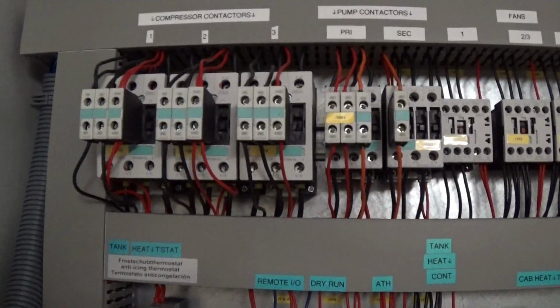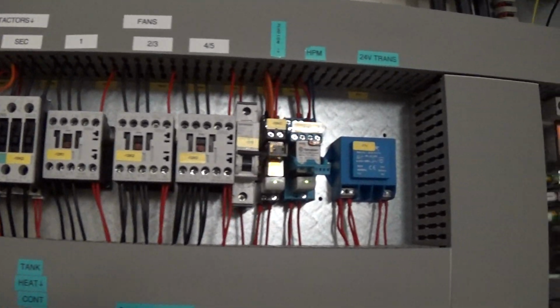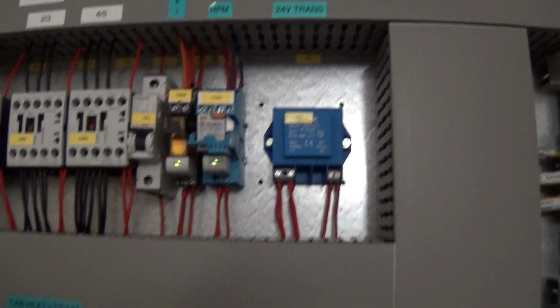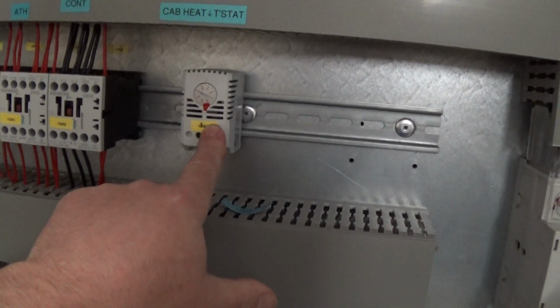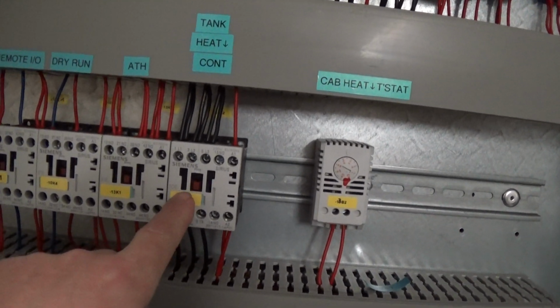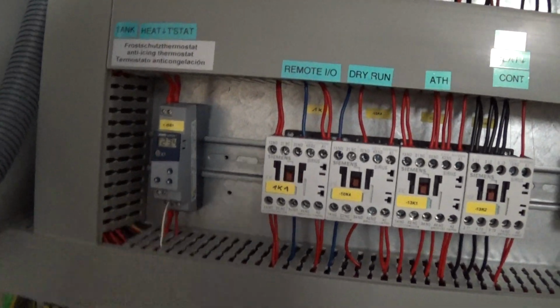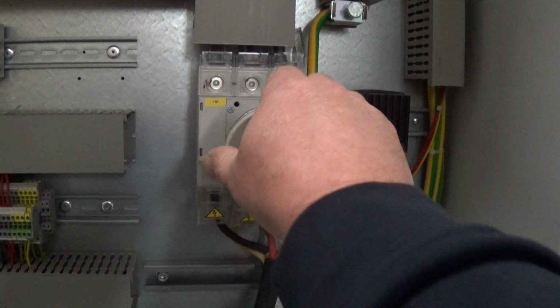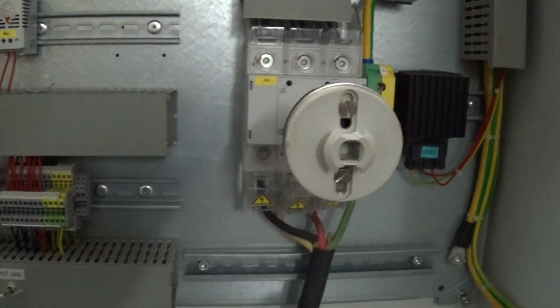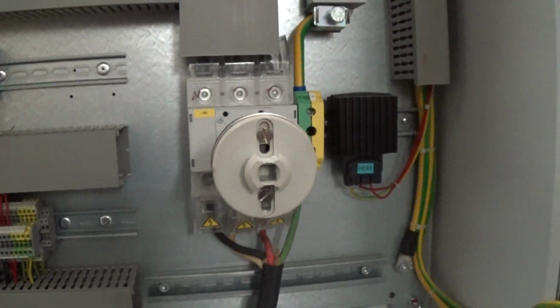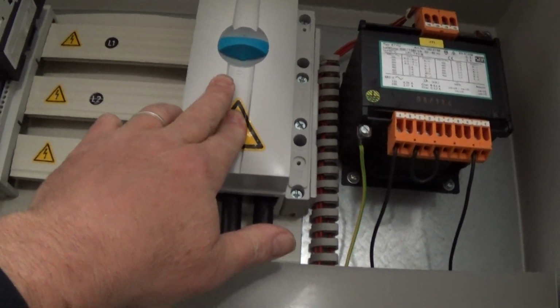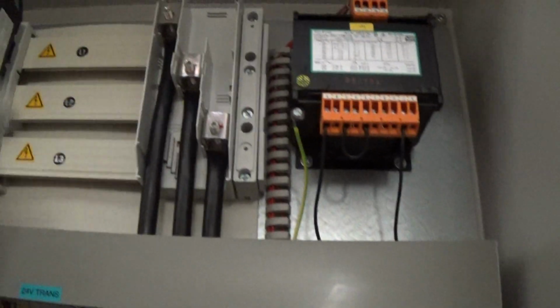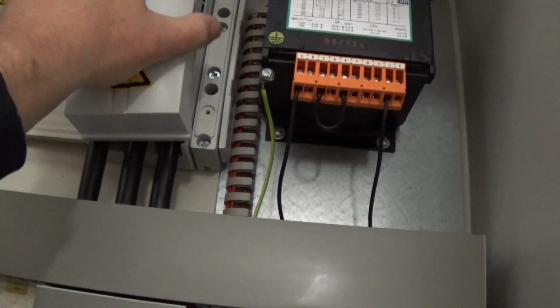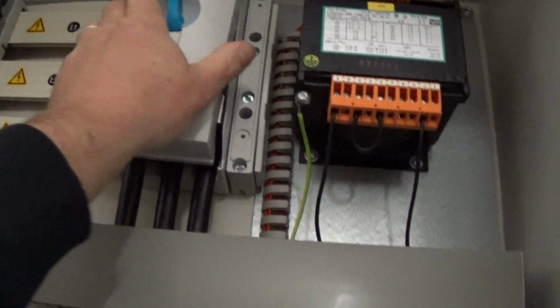Down here we've labeled our compressor contactors, our pump contactors, our fan contactors. We have a cabinet heater thermostat, our tank heater contactor. We have a tank heater thermostat, some of our terminal blocks in here. This is the main power disconnect here for our testing. We manually turn it to the right. Be very careful. Obviously, you should have an electrician power your chiller wiring accordingly. This up here, it looks kind of elaborate. This is nothing more than a cover to cover some of that main incoming wire. Nice little way to do it there.